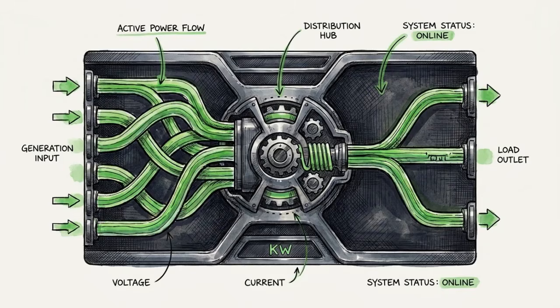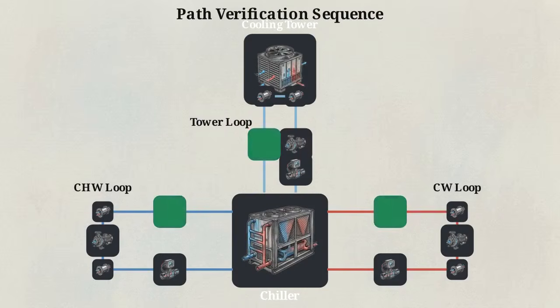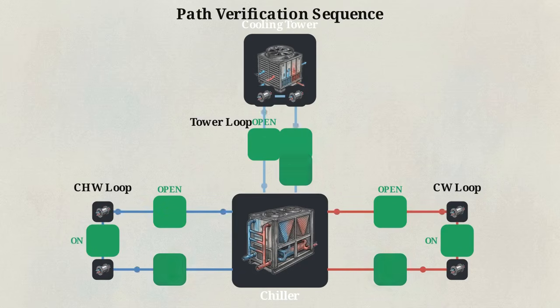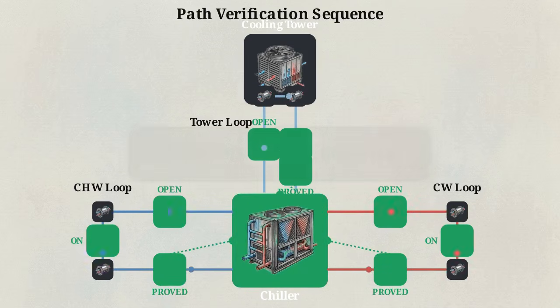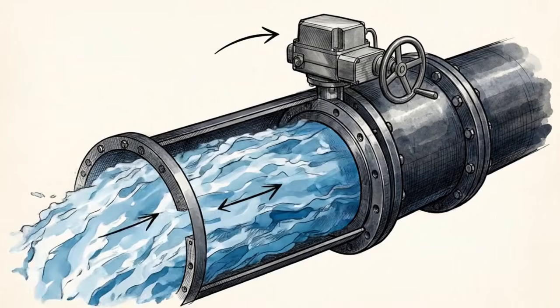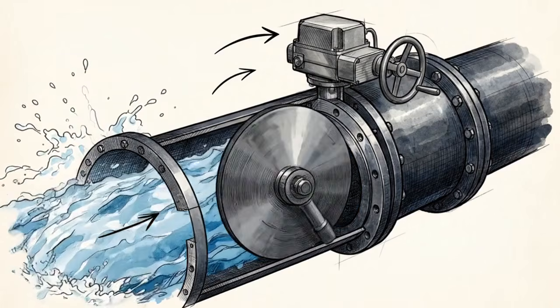Advancing the timeline to the 15 to 25-second window, stable generator power is now flowing, but the chillers themselves remain strictly locked out by the central control system. Before a chiller receives a start permissive, the system executes path verification. Motorized valves stroke open, and independent sensors must physically prove that water is actively flowing through the chilled water, condenser water, and tower loops. Restarting the hydraulic flow across the facility is a massive kinetic event.